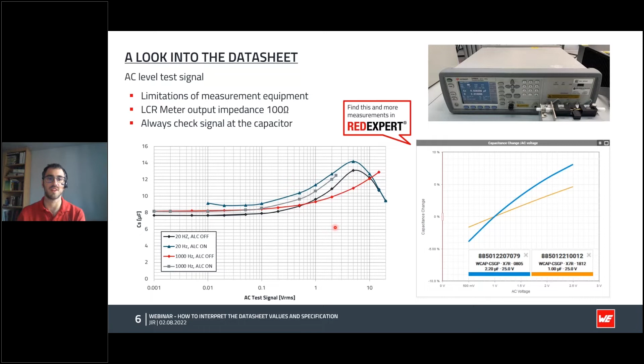So in this graph, you can see different settings with ALC on and off, at 20 hertz and 1000 hertz. All the measurements are different, especially when we change the test signal. So we cannot compare these measurements to each other. We have to know in which settings exactly we are measuring capacitors.